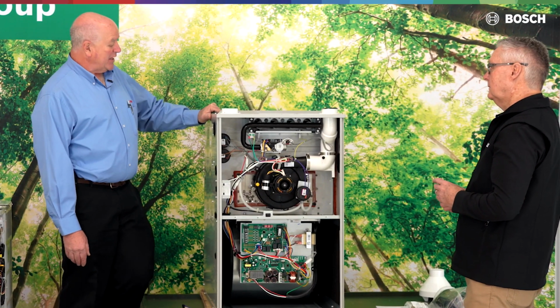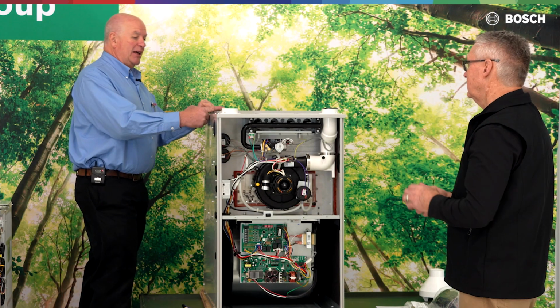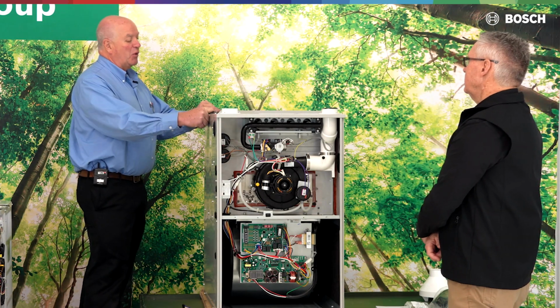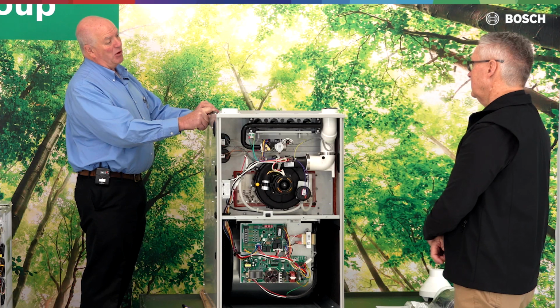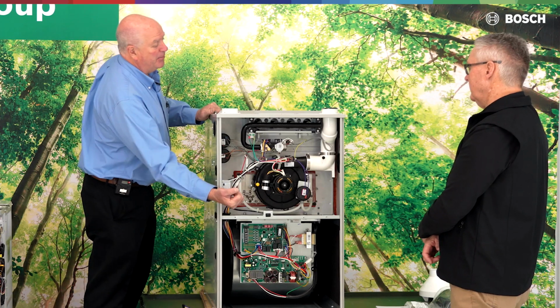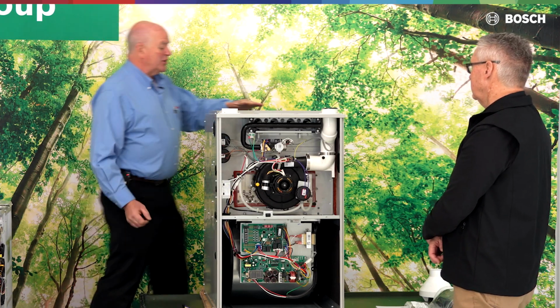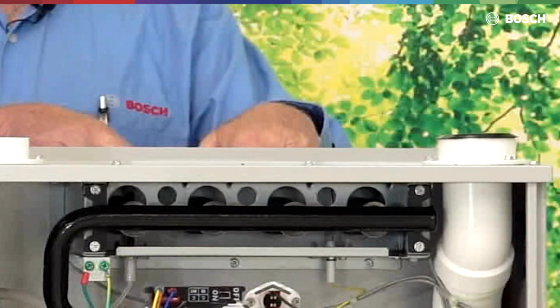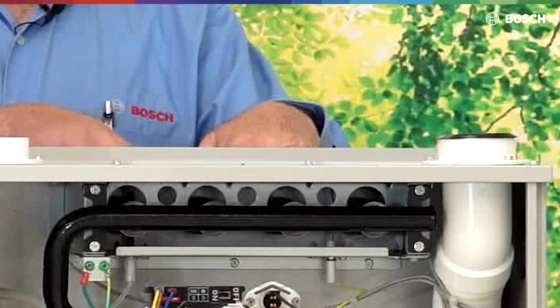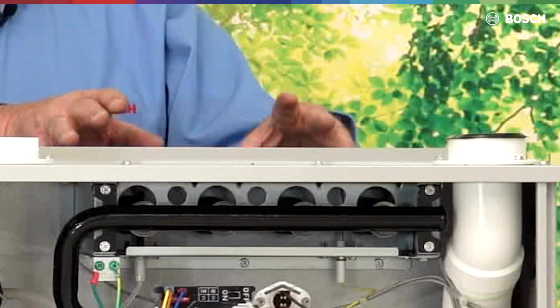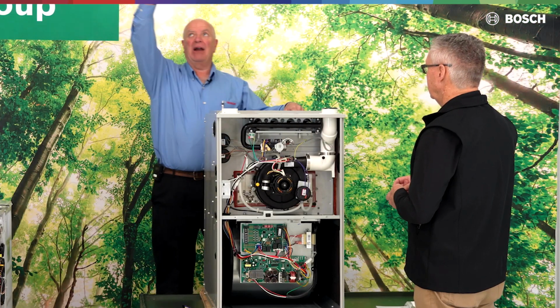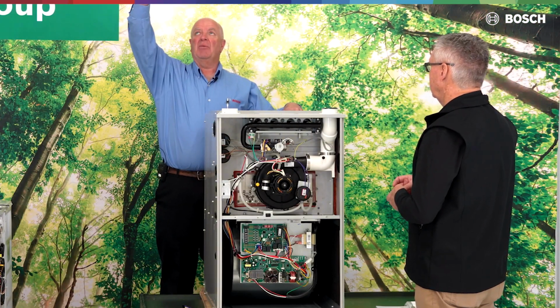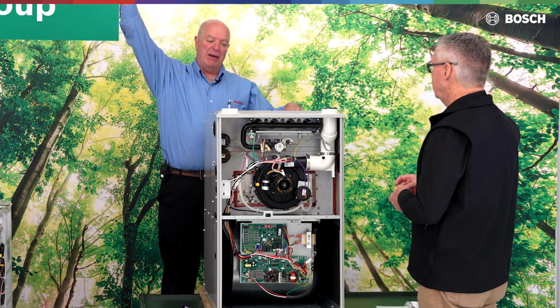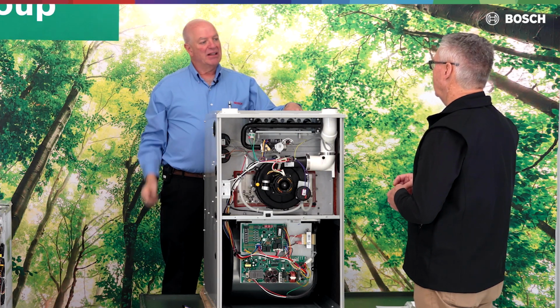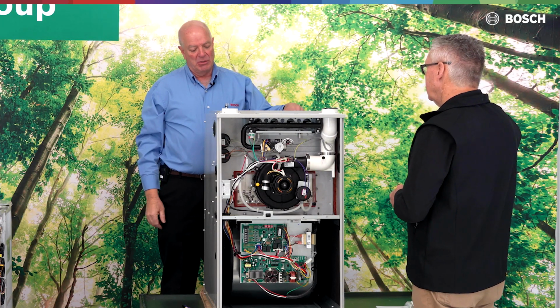If I take my air sensor and come in from the side, I'll get maybe a 10 to 30 degree rise. You'd think you're way under and crank the gas pressure up. But if I come back over to the 4 tubes, right in the center, I can get upwards of a 200 degree rise. So when doing our air temperature rise, we want to be out of sight of these elements, up around the corner of the ductwork. We don't want the thermometer able to physically see the infrared tubes, because they'll give you a bogus reading.